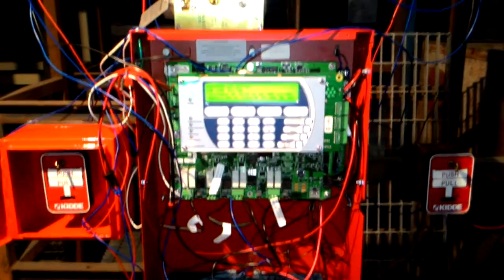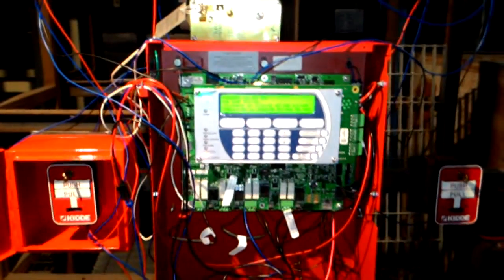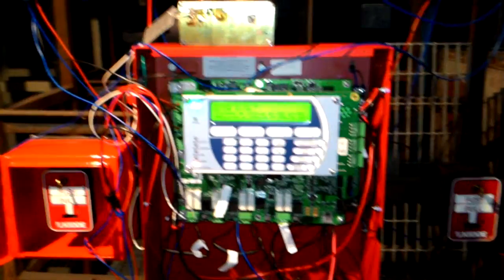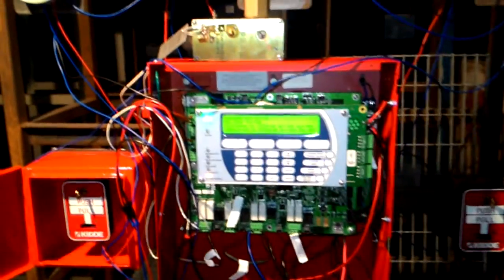In this video, we are demonstrating the cause and effects on an Aries Netlink fire suppression and detection control panel. Now, the first cause would be the activation of smoke detector that is addressed as one in the loop, or could be the second smoke detector.